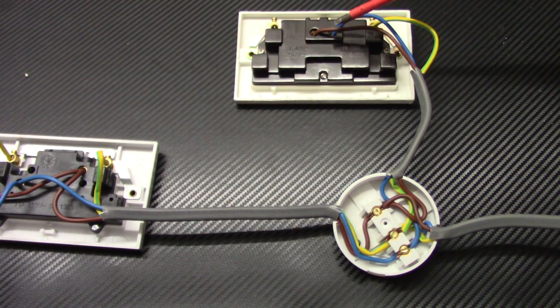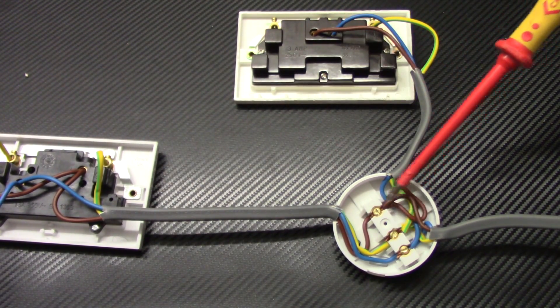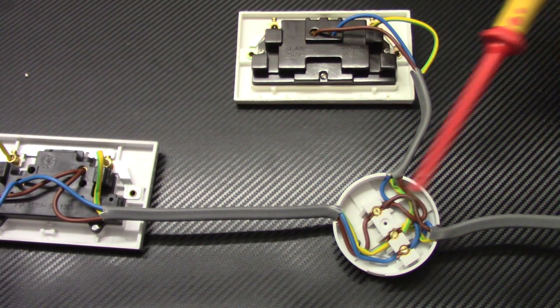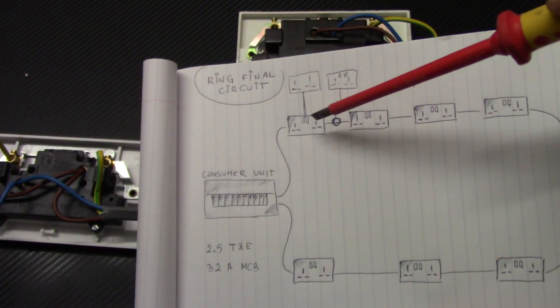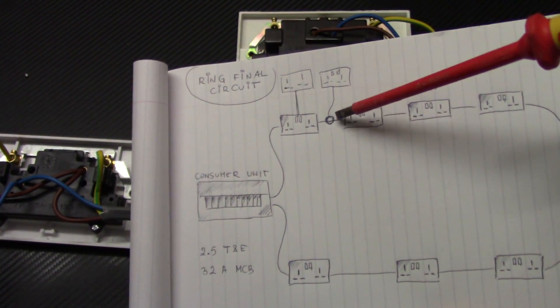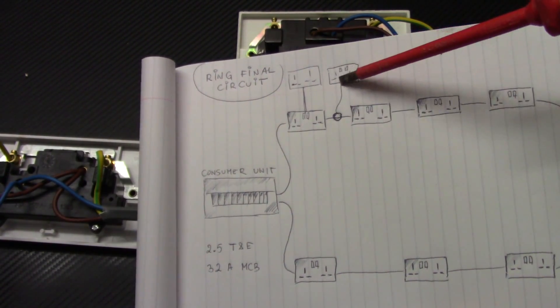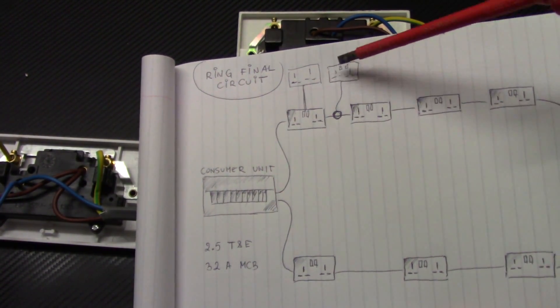So that's the spur taken from the junction box fitted on the ring cable in between two socket outlets. What I've done, basically, between two sockets I cut the cable, fitted the junction box, and I connected another socket outlet which is our spur.